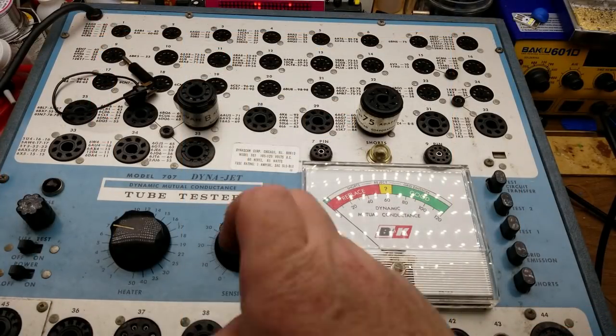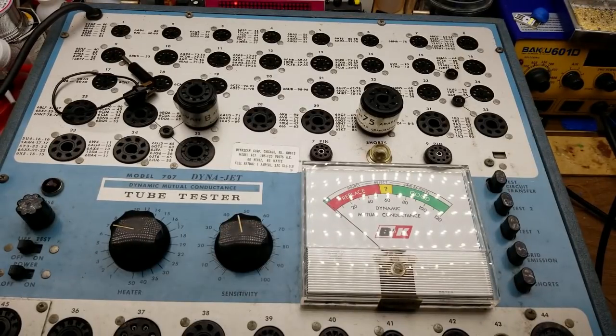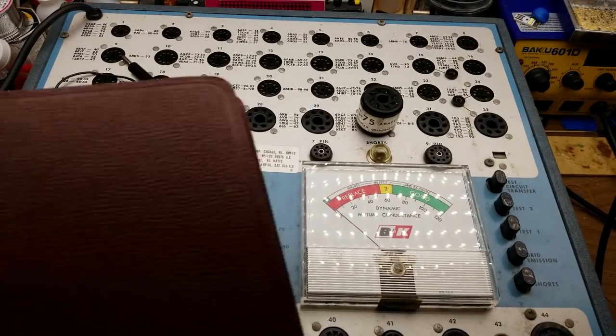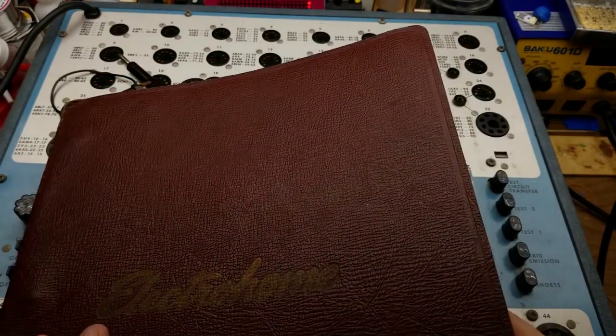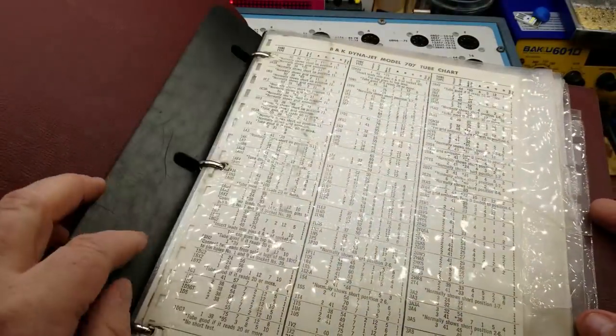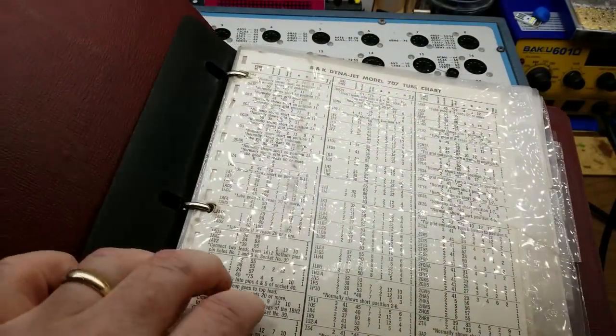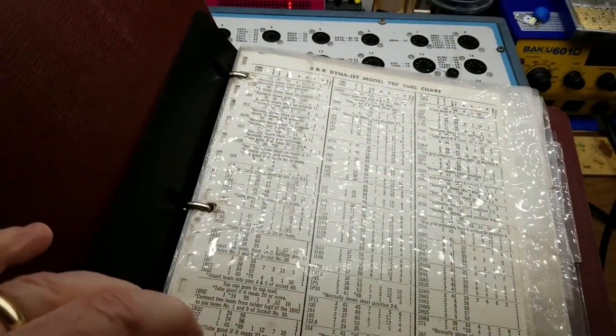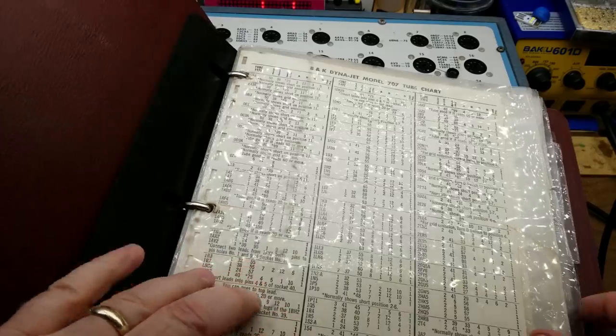Okay, so here's how somebody would use this thing. The first thing you need is the book that comes with it. This one's been sort of rebound, but it has a list of all the different tube types that you can test on this thing and the settings and everything that you use.